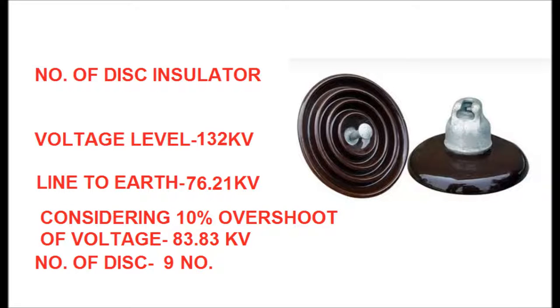For the 132 kV system, the line-to-line voltage is 132 kV. The line-to-earth voltage is 132 divided by √3, equal to 76.21 kV. Considering 10% overvoltage: 76.21 × 1.1 = 83.83 kV. Dividing 83.83 by 11 gives approximately 8. Adding 1 for safety margin gives 9 discs for suspension type string and 10 discs for tension type string in a 132 kV system.